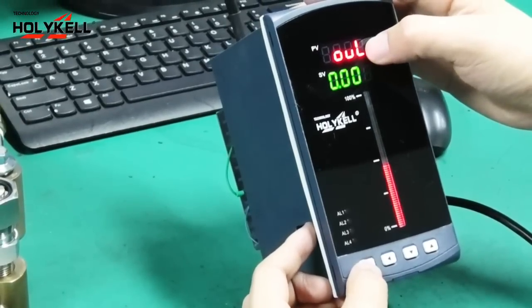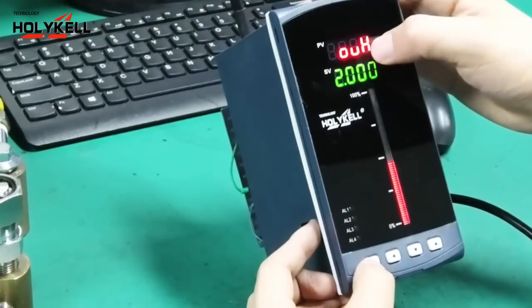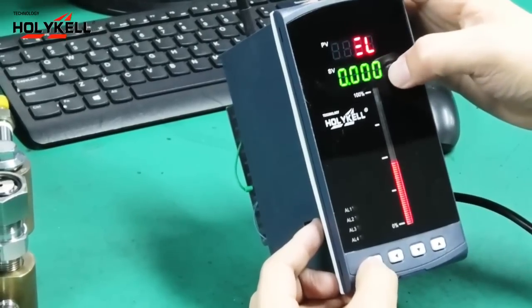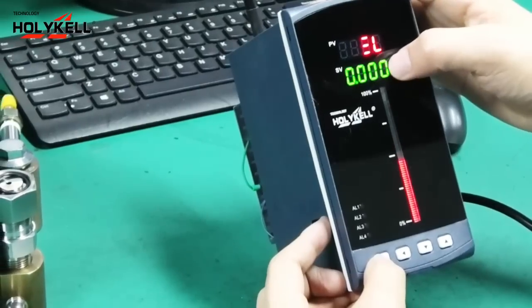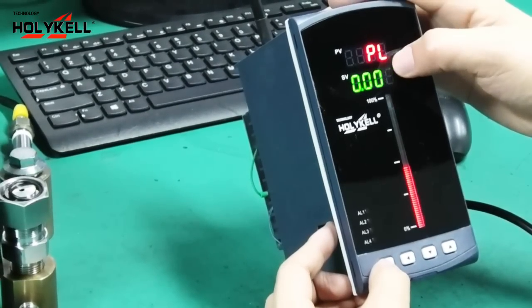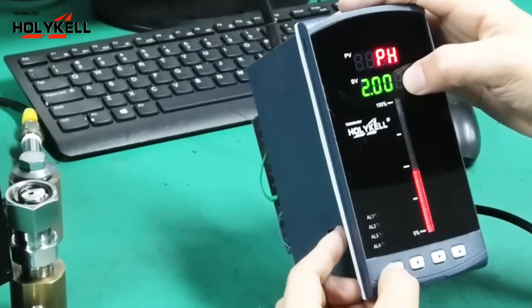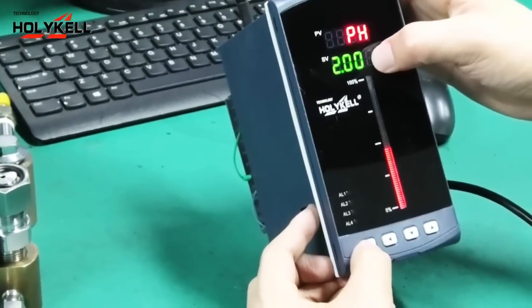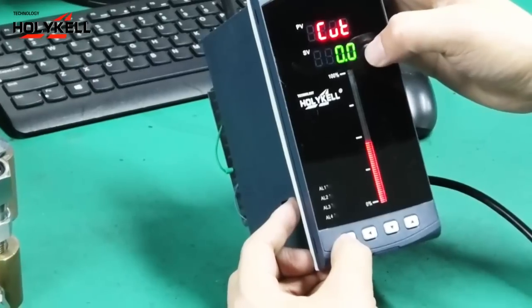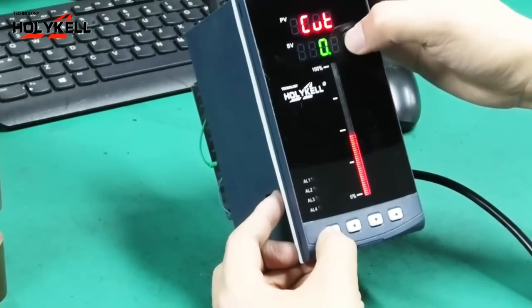Set OUL — the lower range — to zero meters, and PH — the upper range — to two meters. This is the same as the level range setting. The EL parameter is the same as the level lower setting. No additional settings are needed for the single cut parameter.